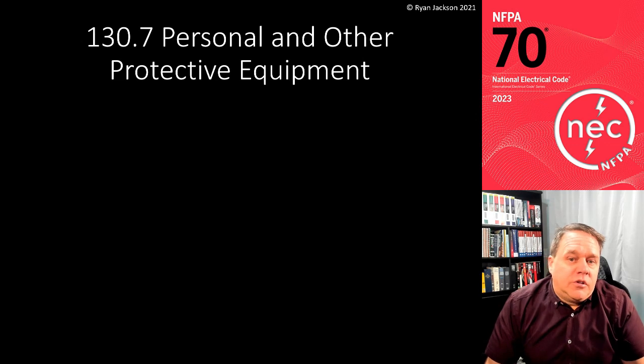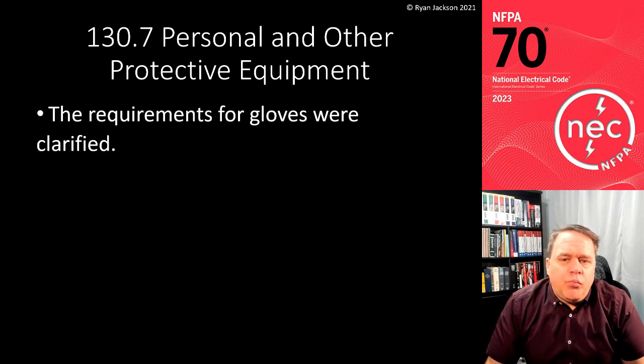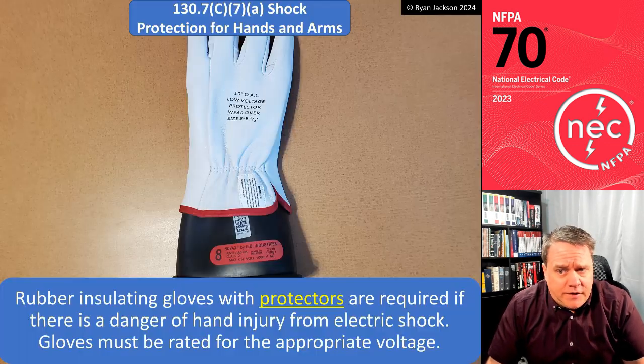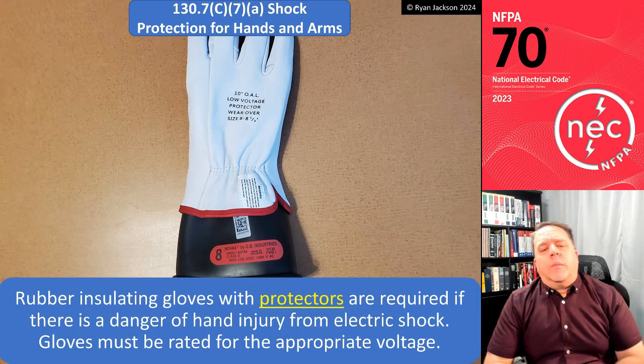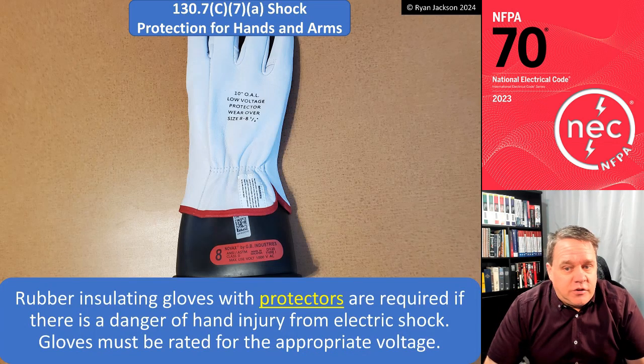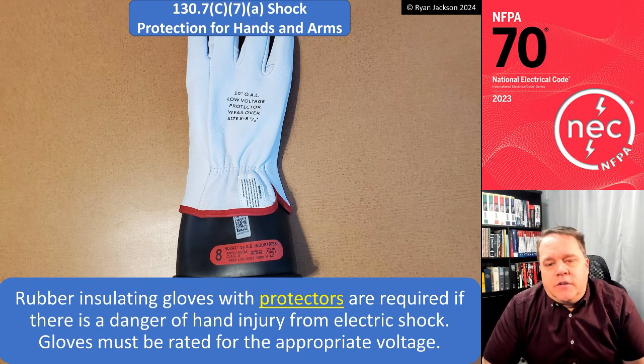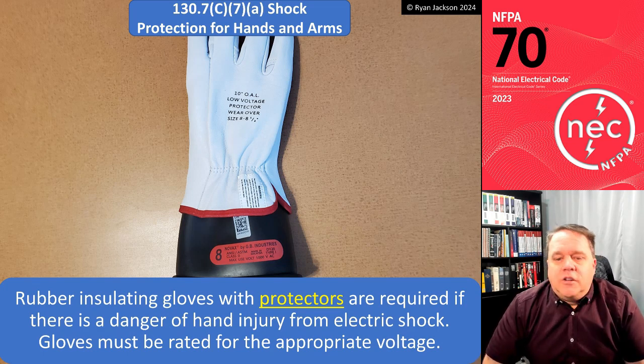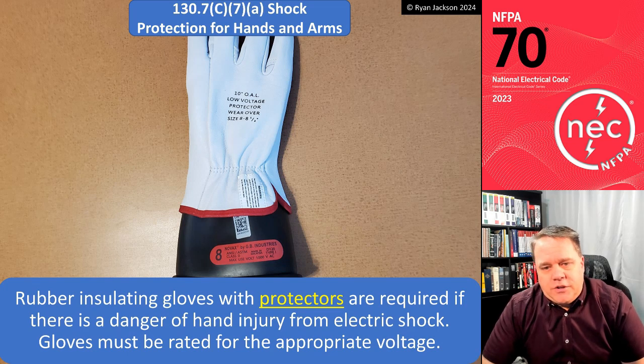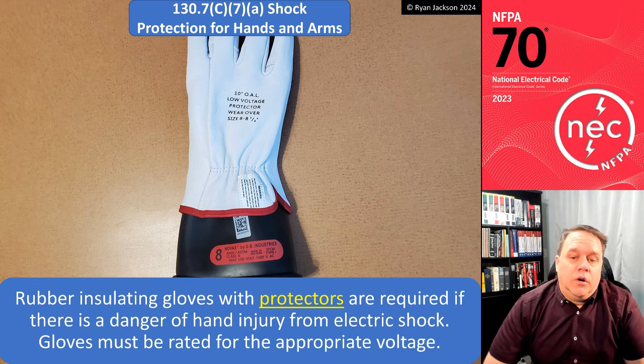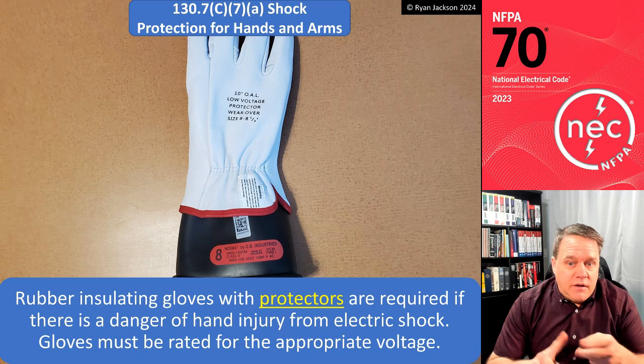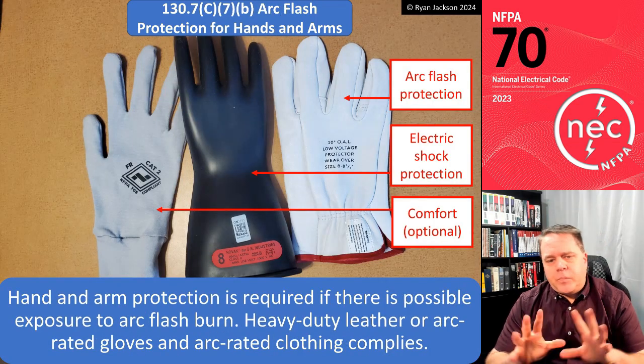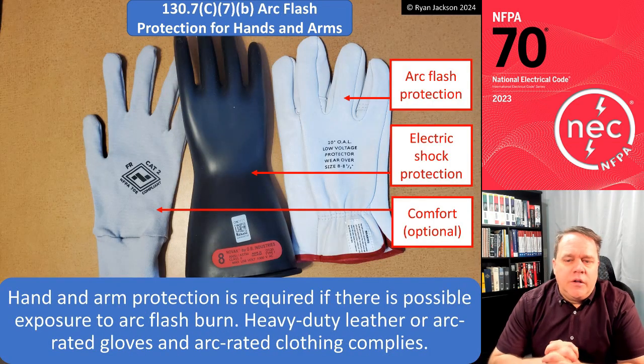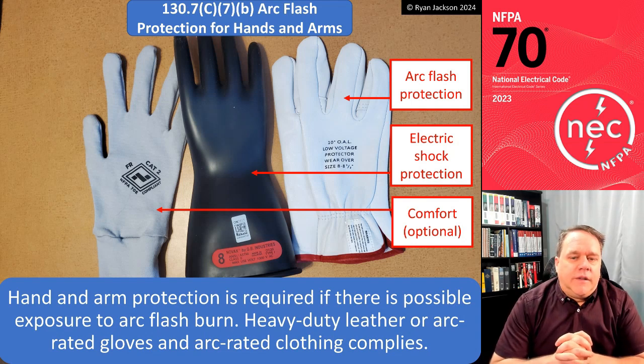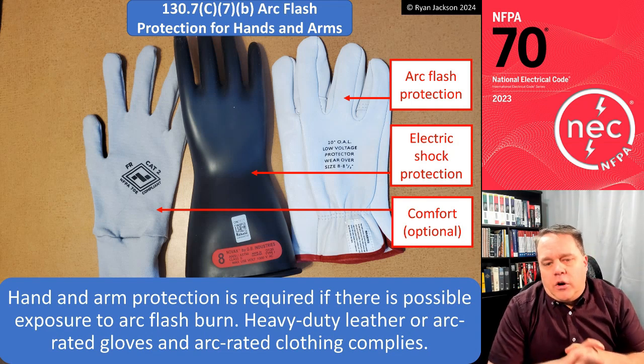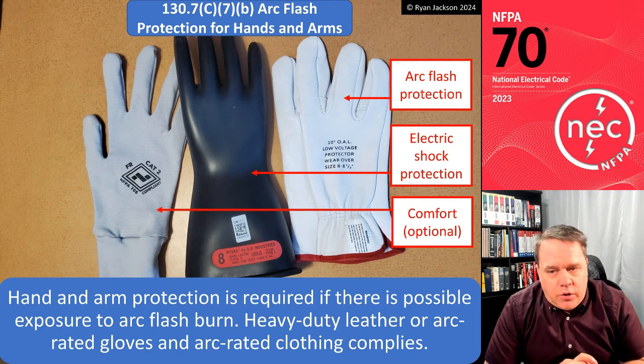130.7, personal and other protective equipment. The rules for gloves were clarified. Okay, so rubber insulating gloves with protectors are required if there's a danger of hand injury from electric shock. Gloves have to be rated for the appropriate voltage. All right, so here in the picture, you've got your rubber insulating gloves, and you've got your protector over it. And hand and arm protection is required if there's possible exposure to arc flash burn. Heavy-duty leather or arc-rated gloves and arc-rated clothing complies.